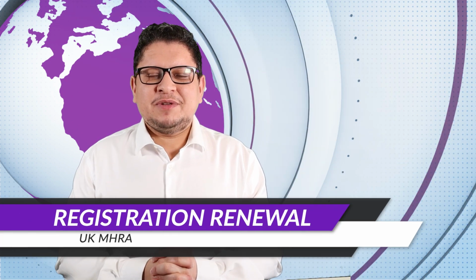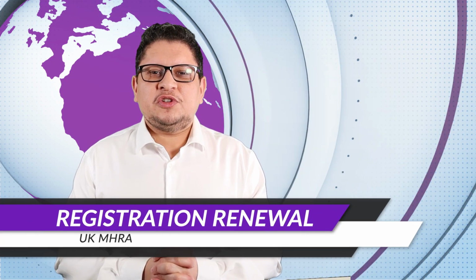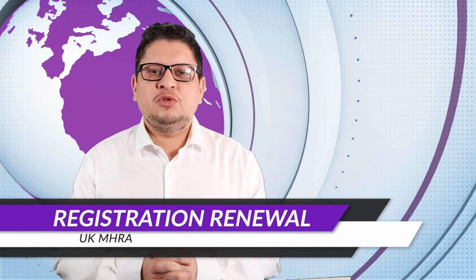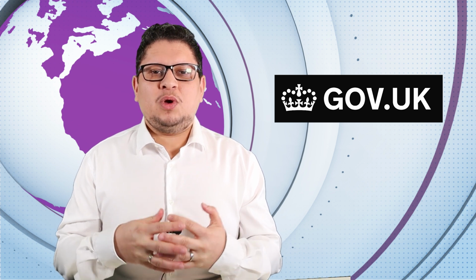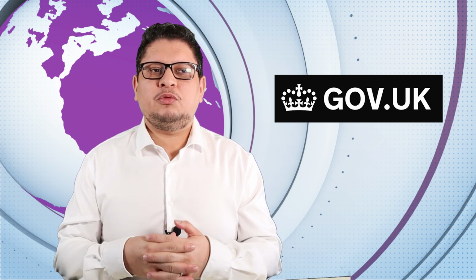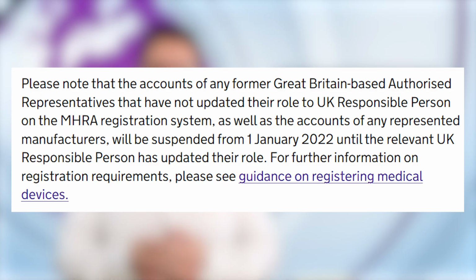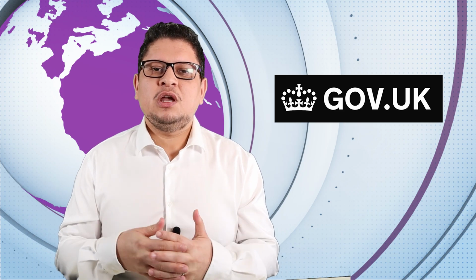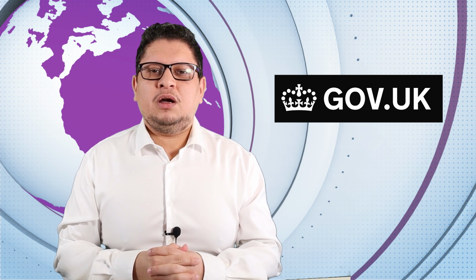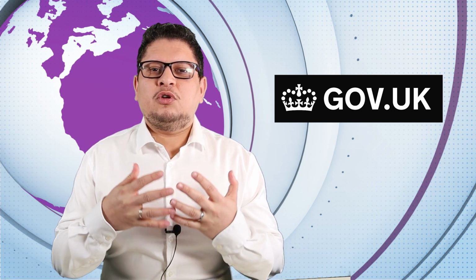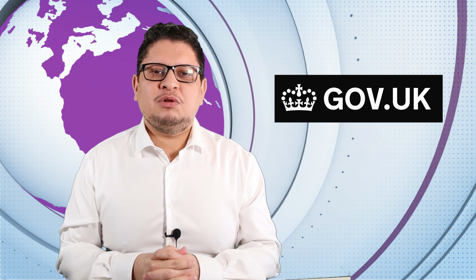UK, with the UK responsible person. So from January 1st, 2022, we had some updates to the UK regulation requirements. And one of the changes is the fact that you now have to register or re-evaluate your registration on the MHRA website. So if you are a UK responsible person, you will have, like me, because we are also one, a lot of communication maybe from your customers, because they will receive a message 3 months before the anniversary date for the renewal of their registration within the MHRA database.